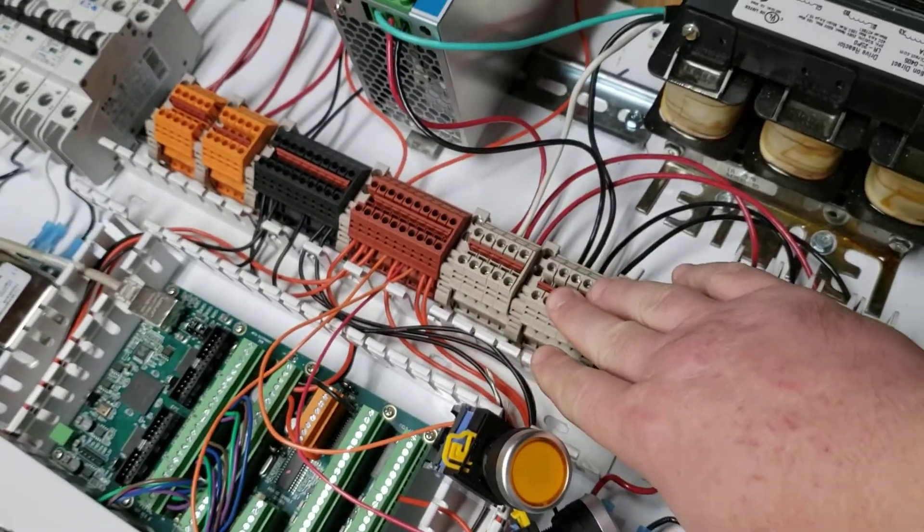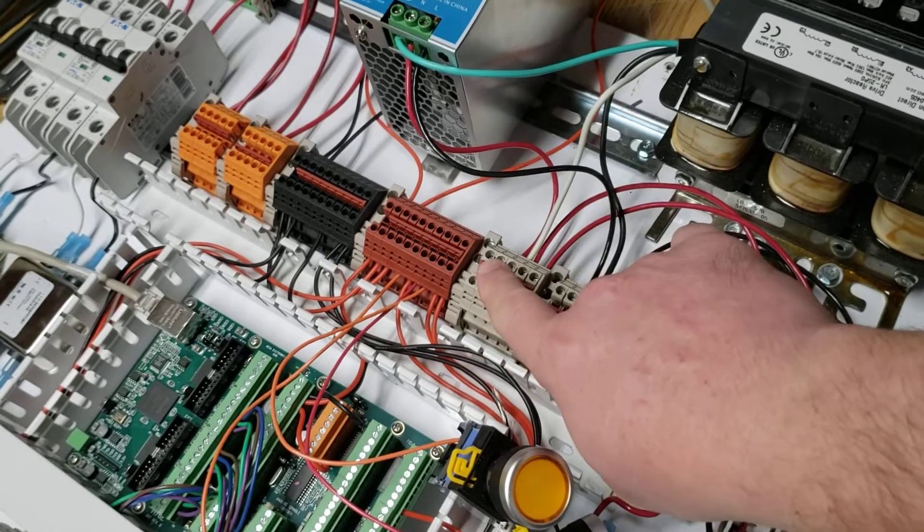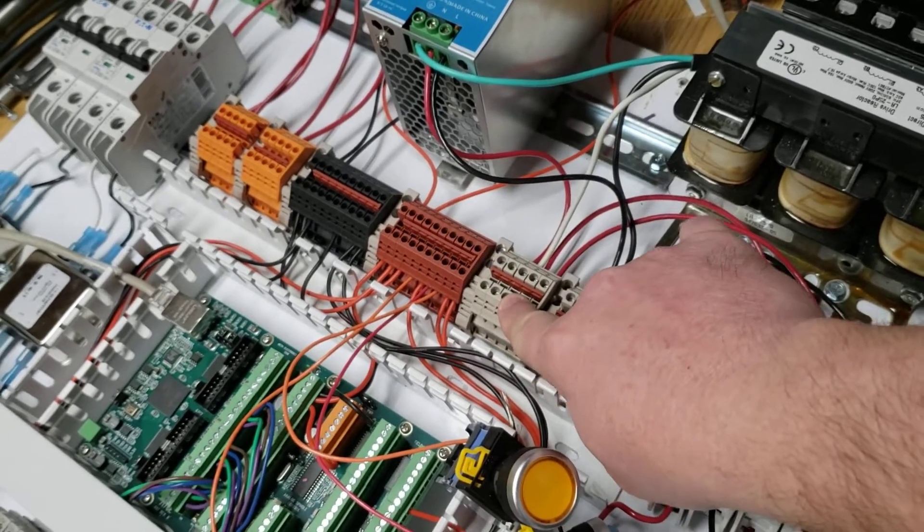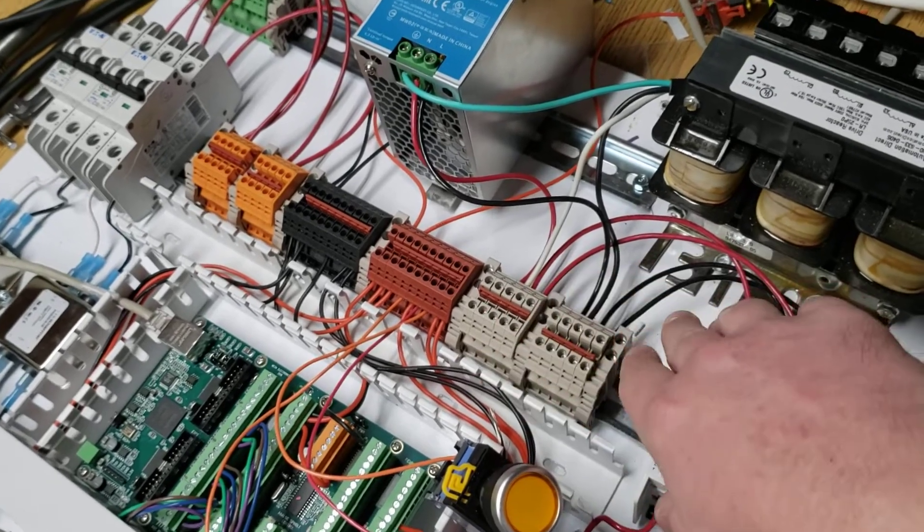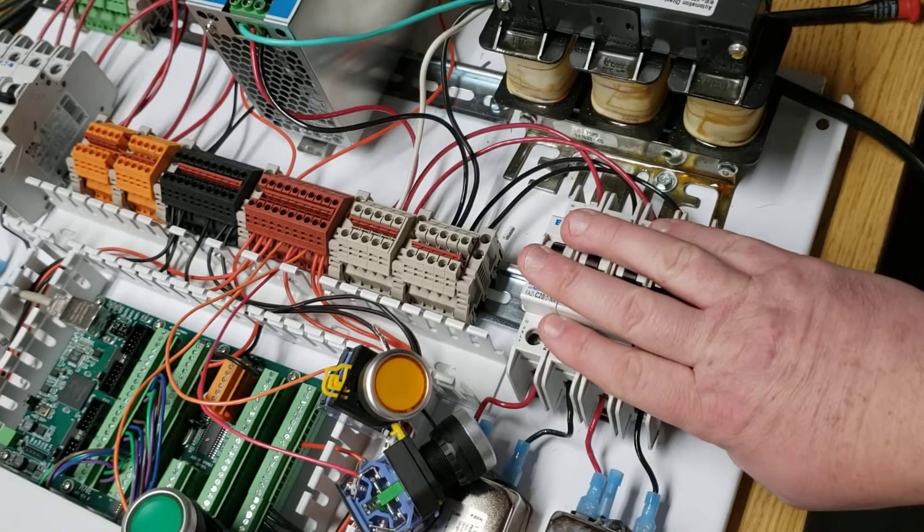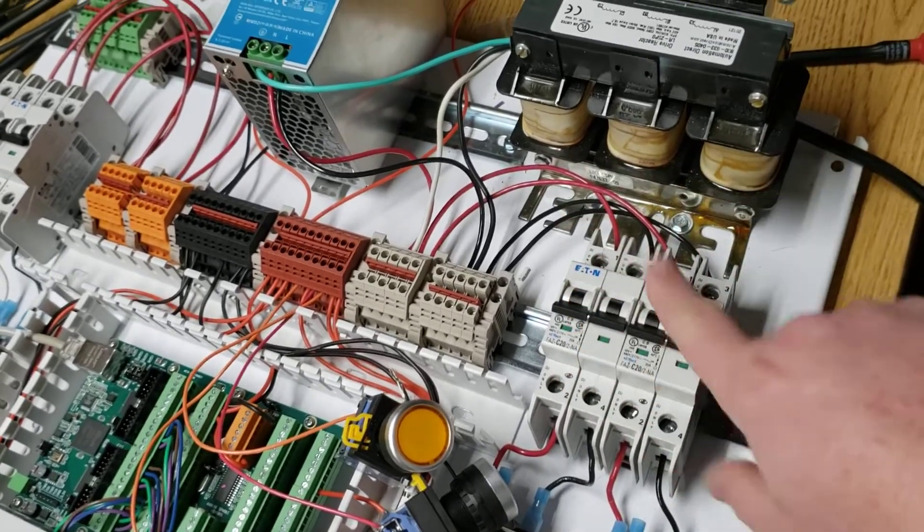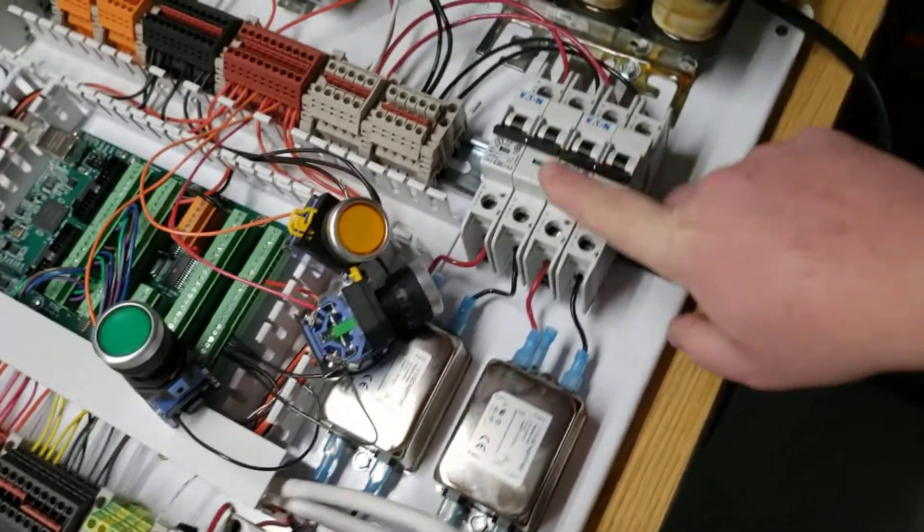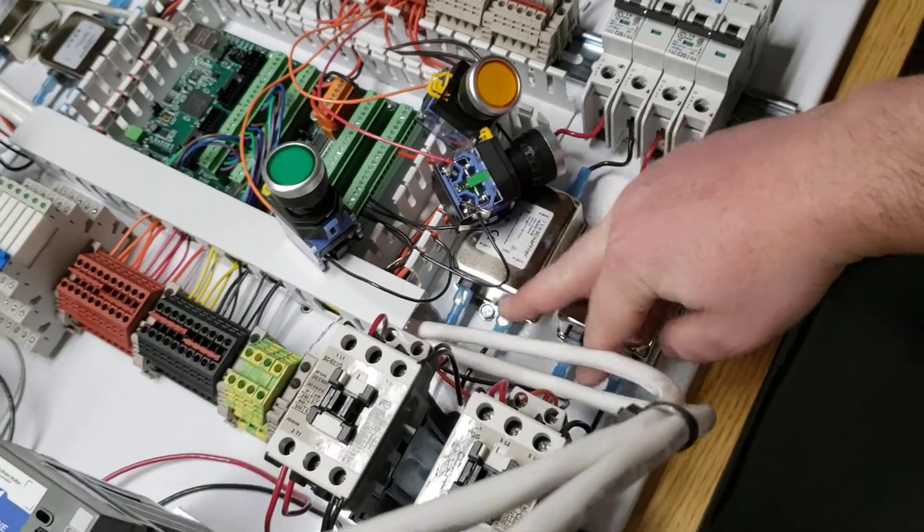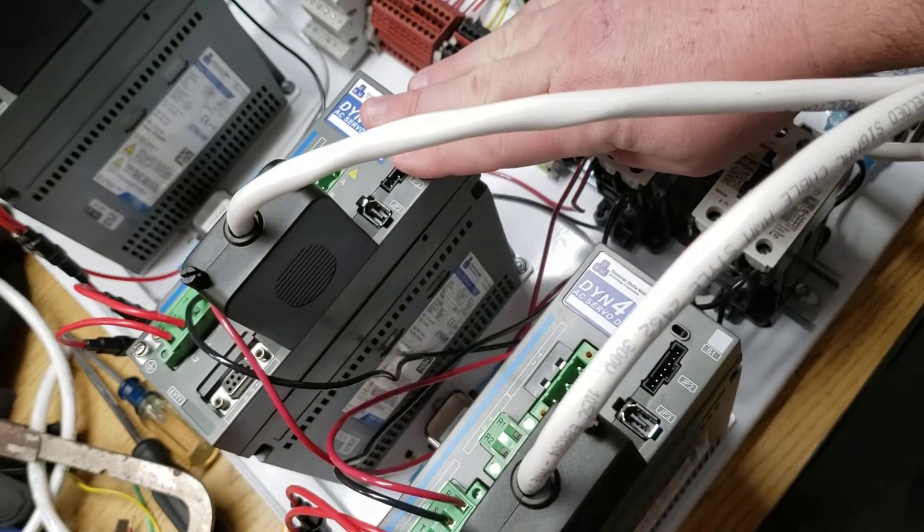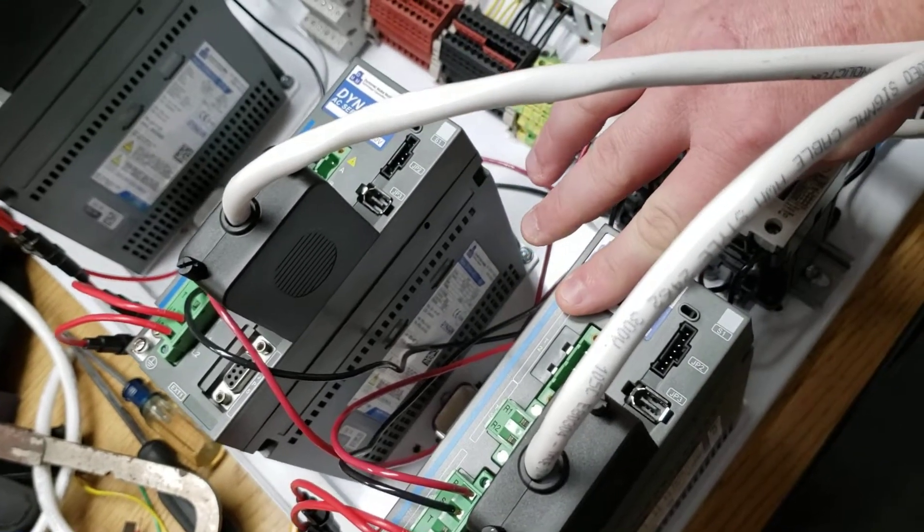The rightmost terminal block is 220 red leg and 220 black leg in and out. Out to the right side of the panel, two breakers. Those two breakers then come down to two noise filters. From the noise filters, they go to two contactors, and one feeds this drive, and one feeds this drive, both in 220.